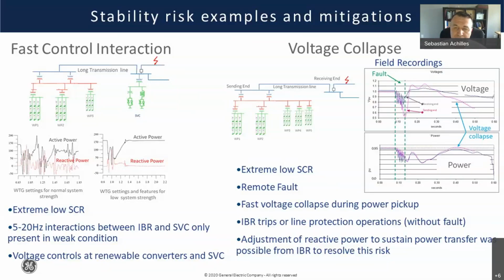So in this case, between the green markers, you see the fault time, and there is kind of an oscillatory behavior. That's actually not an oscillation, it's the effect of the unbalanced fault. When you calculate the positive sequence quantities with the unbalanced fault, it looks like that. It's not really an oscillation, it's just a mathematical artifact of calculating positive sequence quantities with several sequences present.